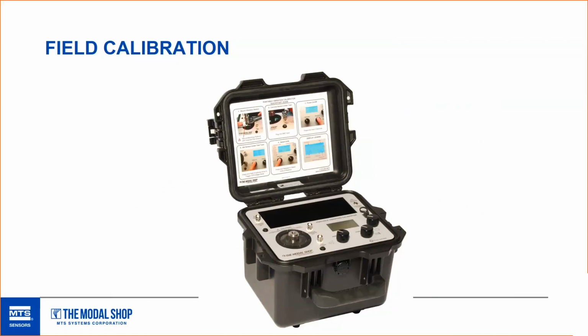Modal Shop makes this portable vibration calibration device that operates over a wide frequency and amplitude range, and it has a built-in traceable reference accelerometer. It can even create a traceable CalCert, but at a trade-off for uncertainty from sending it into a pro lab or someone using one of the Modal Shop, for example, Cal workstations.